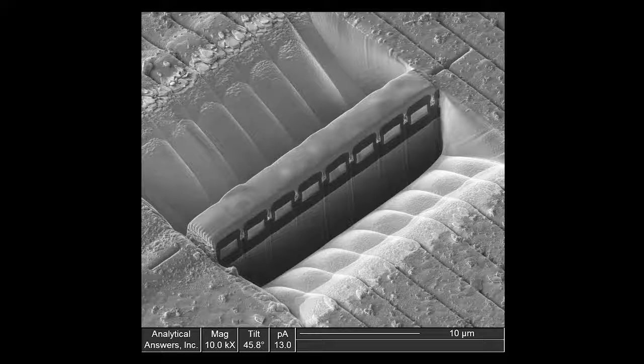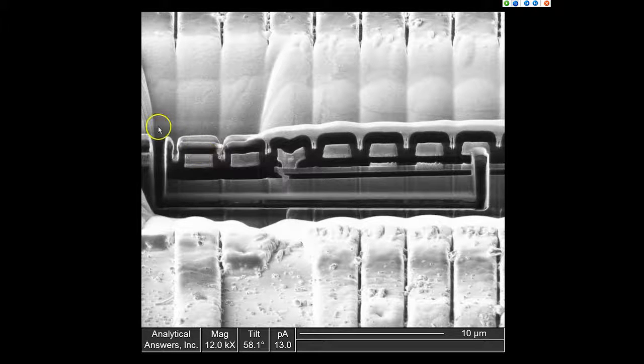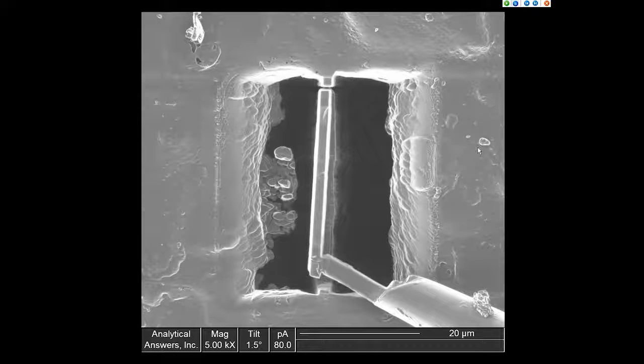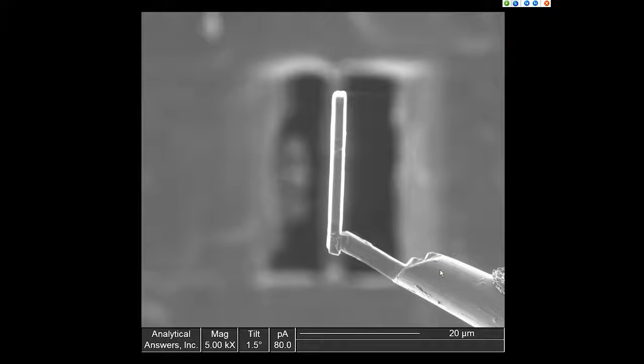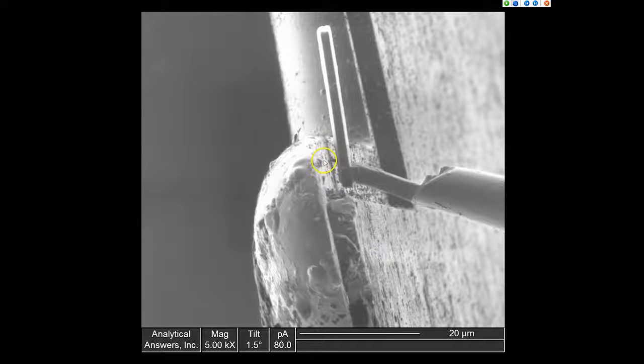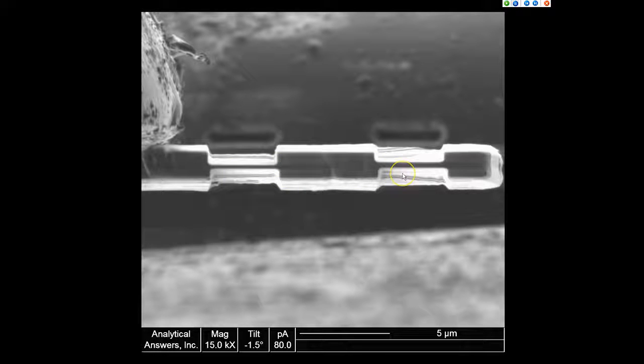So to make a cross-section thin sample in the FIB, you basically perform 2 FIB cross-sections, one in each direction around the feature of interest coming from the front and the rear. And then you come in and you undercut that with the same FIB beam. You're able to take that little coupon and pick it up on the end of a probe and free it from the substrate and then attach it to a sample holder, which then would allow you to pass the electron beam through it once you've thinned it down in the appropriate locations, so that the electron beam will now go through the sample where it's very thin in order to give you that increased spatial resolution in a TEM and the much smaller EDS volume in an STEM.